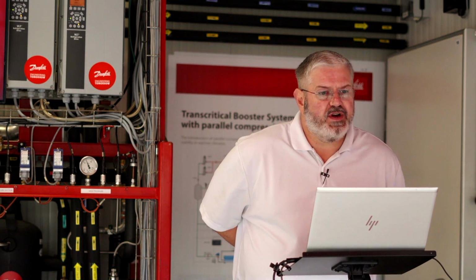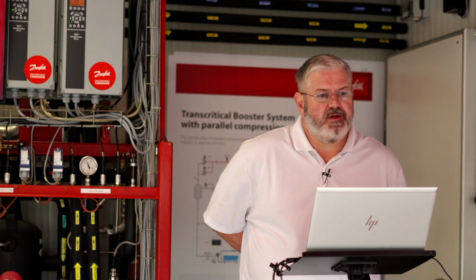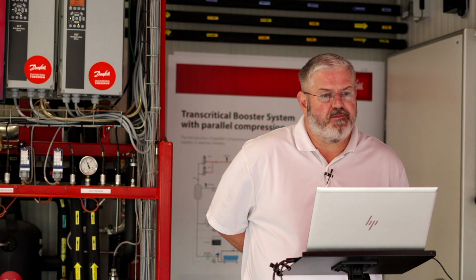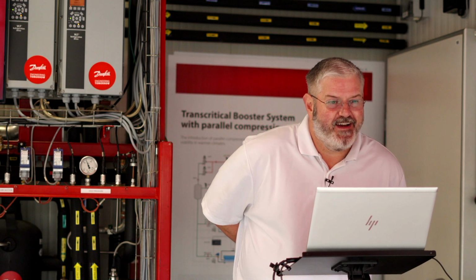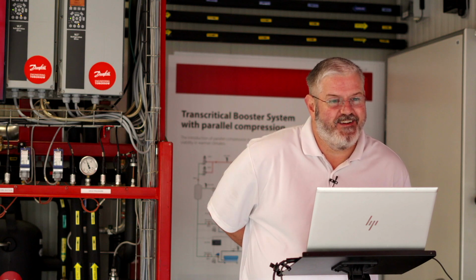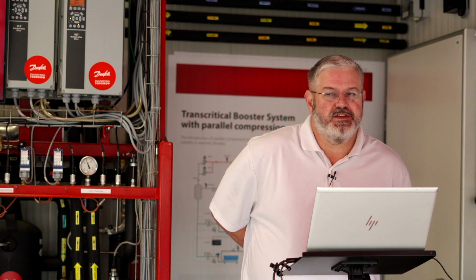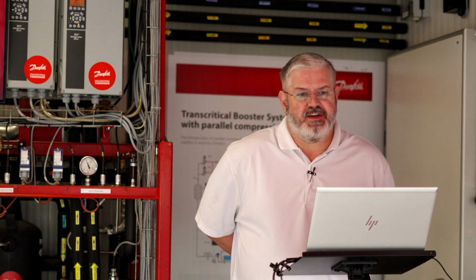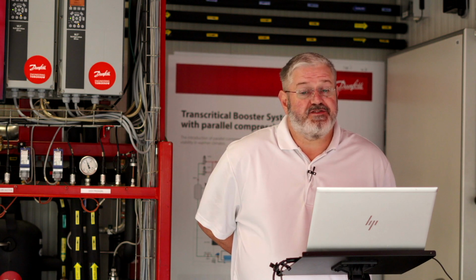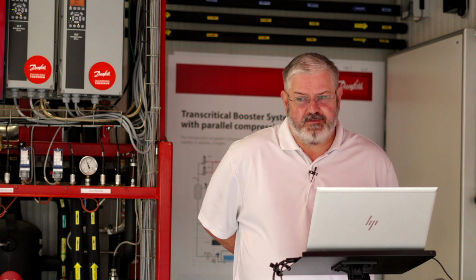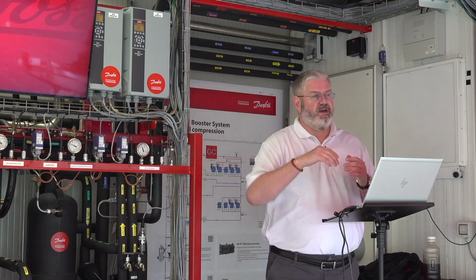And we have another question. In a booster system, if the medium temp compressor is shut down for any operational reason, do the low temp compressors also need to shut down? The answer to that is yes. Typically, it's tied into the software.